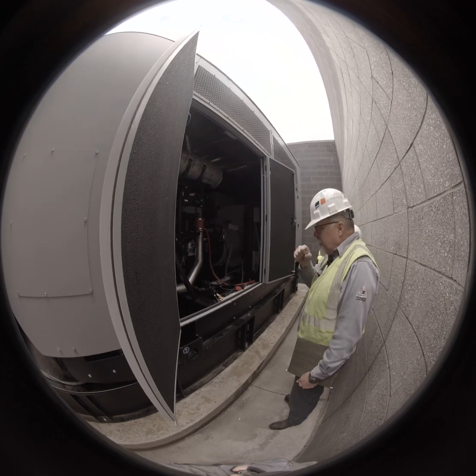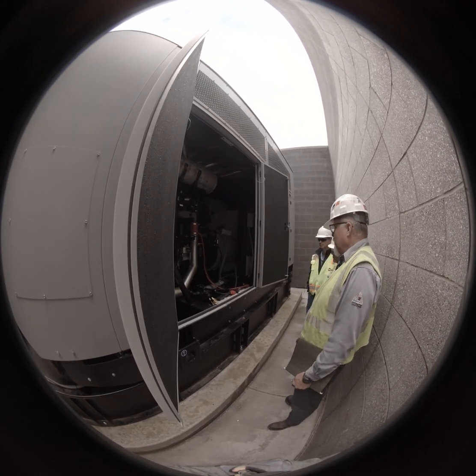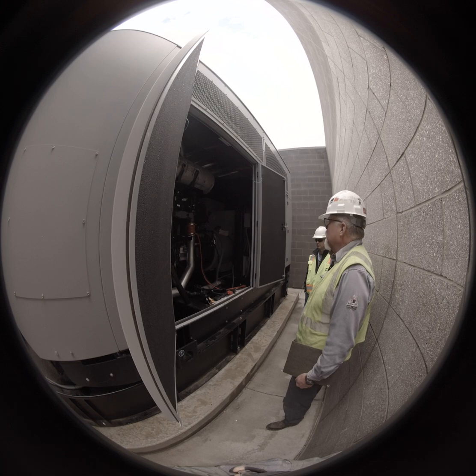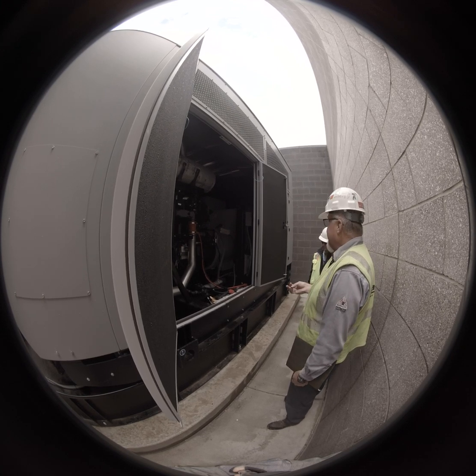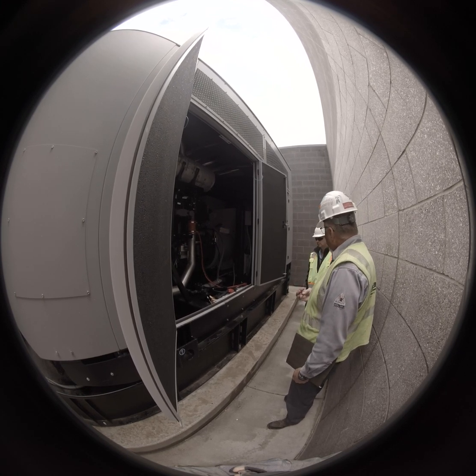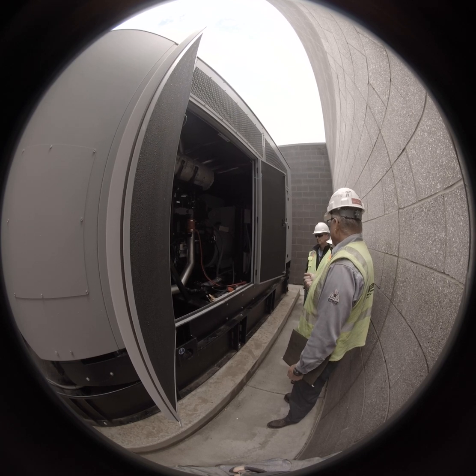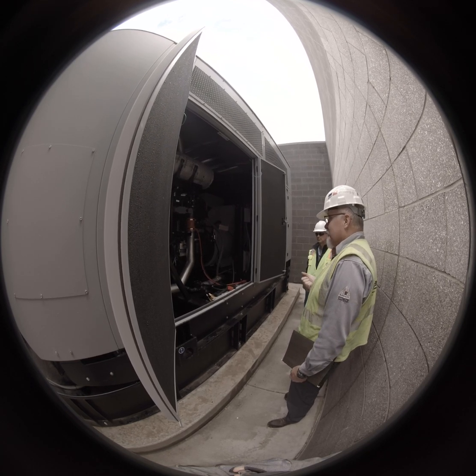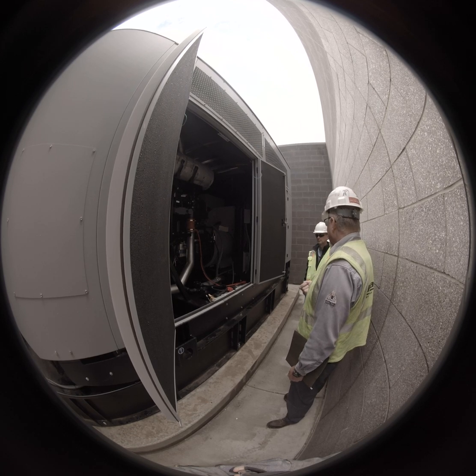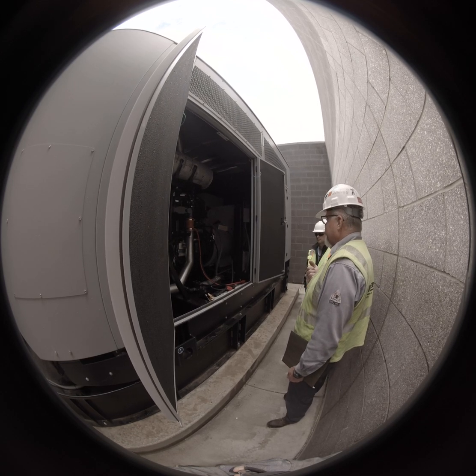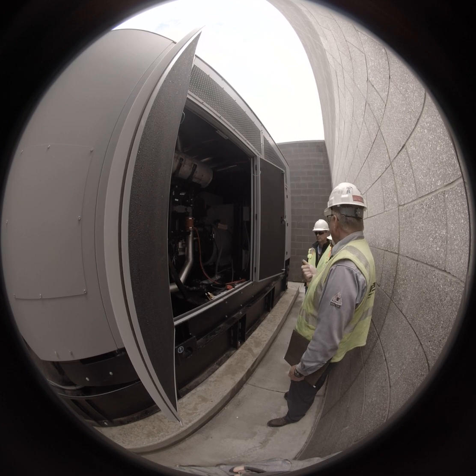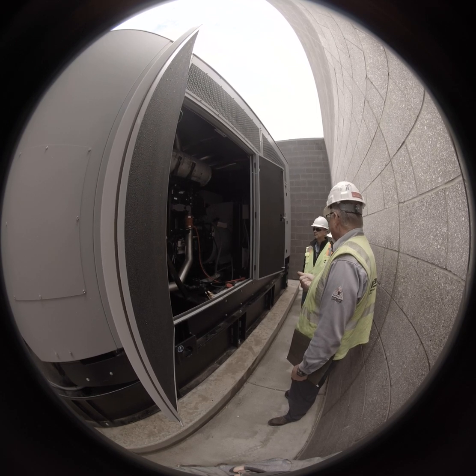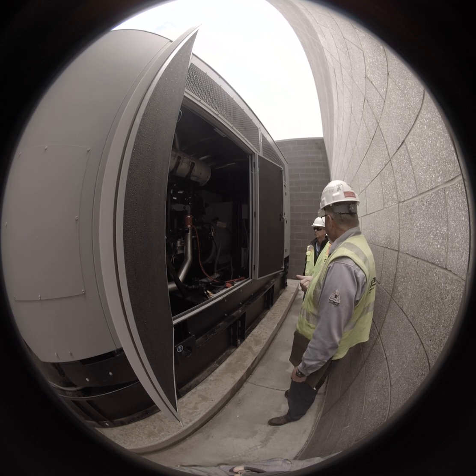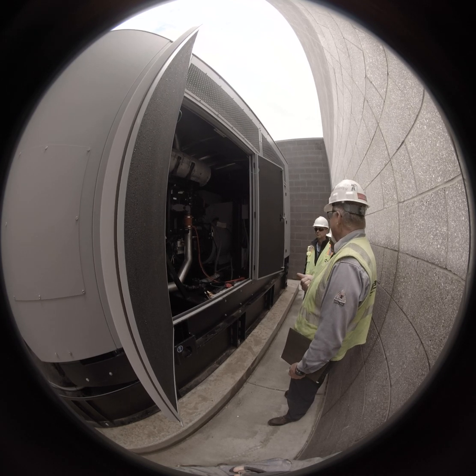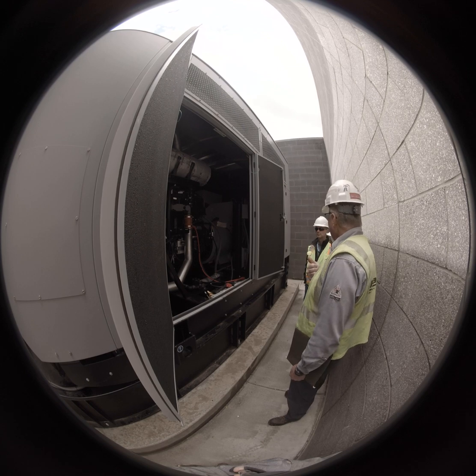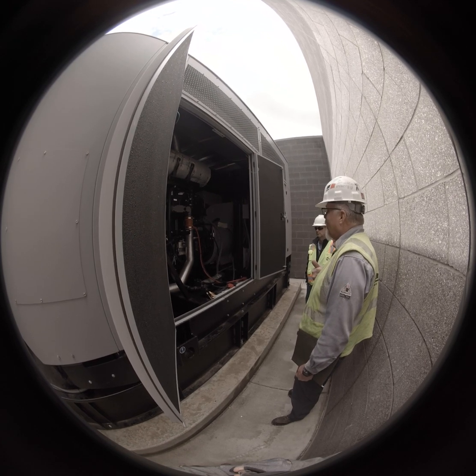Right here in front of us is the engine coolant heater. The engine coolant heater serves two purposes. One is, of course, when it's cold outside, it will allow you to start this engine. You get a cold engine, diesel especially, and they will be sluggish starting. The second purpose for this heater is this is an NFPA 110 compliant generator set. This thing will be online in 10 seconds. So you really don't want an engine sitting at 38 degrees to assume your load in 10 seconds. It is hard on engines.